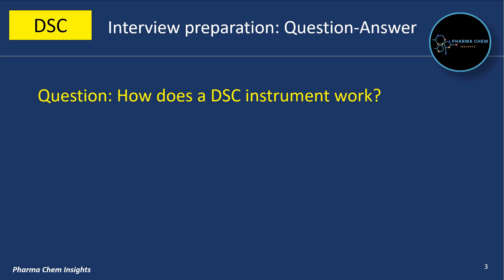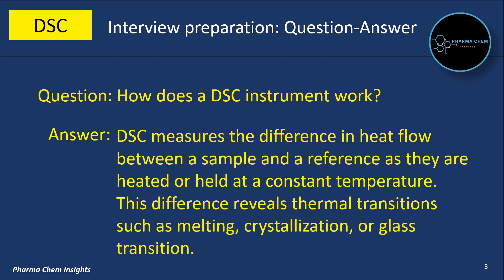Next question: How does a DSC instrument work? DSC measures the difference in heat flow between a sample and a reference as they are heated or held at a constant temperature. The difference reveals thermal transitions such as melting, crystallization, or glass transition temperature.